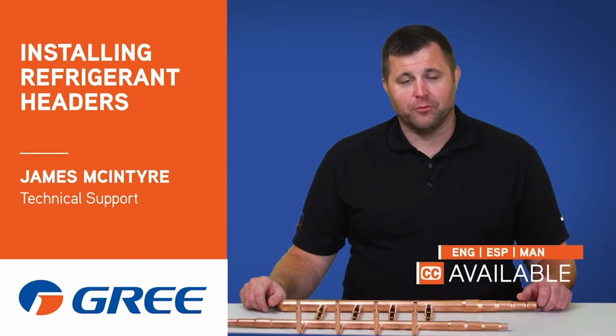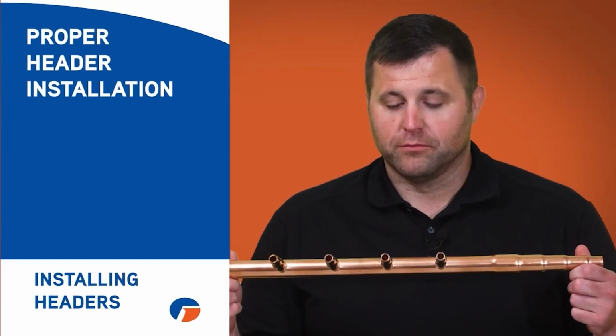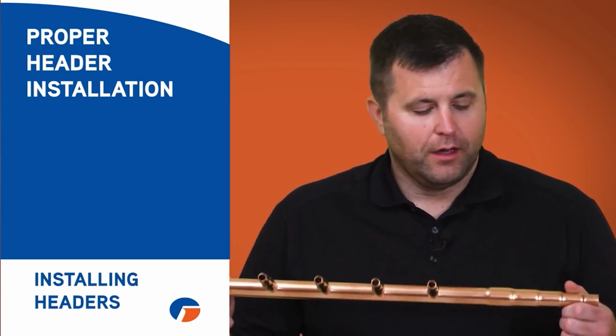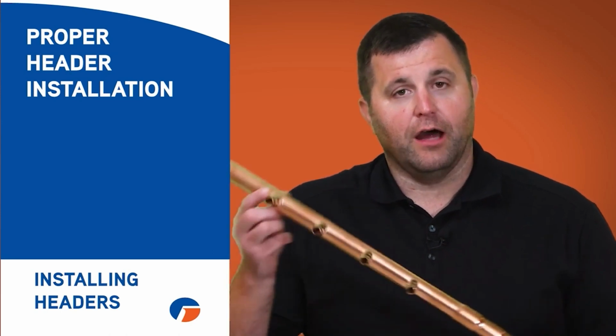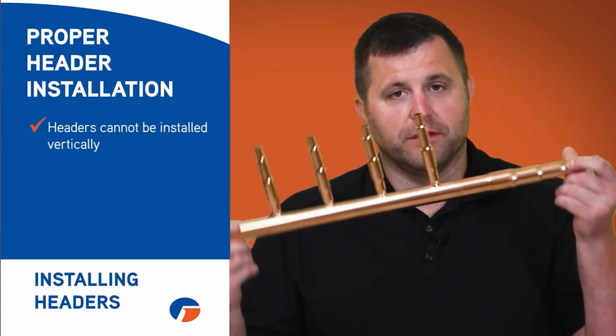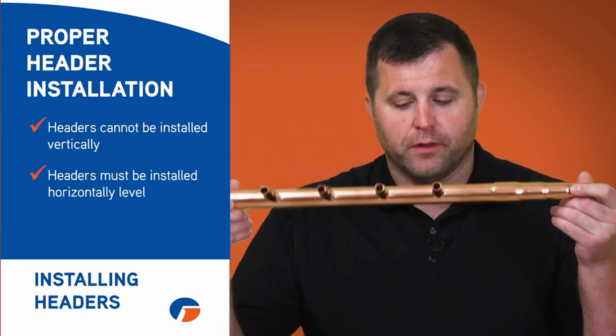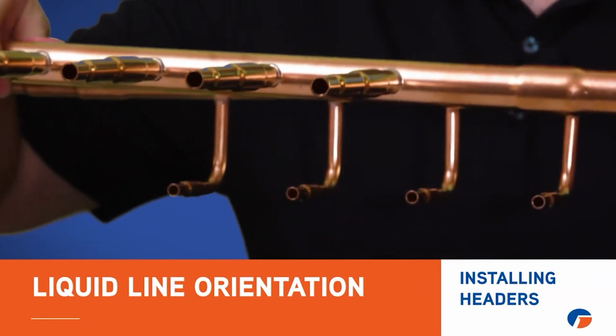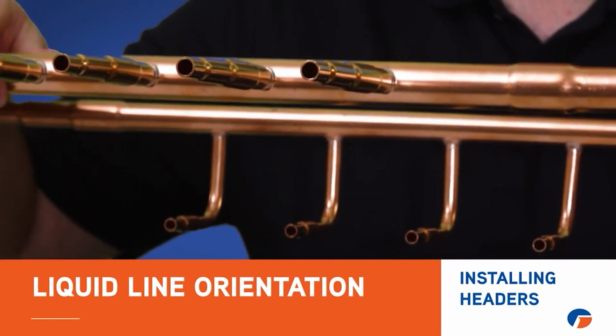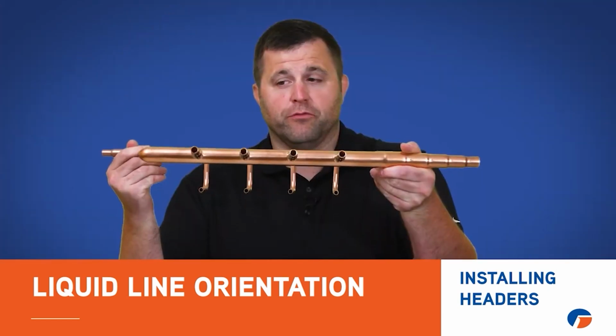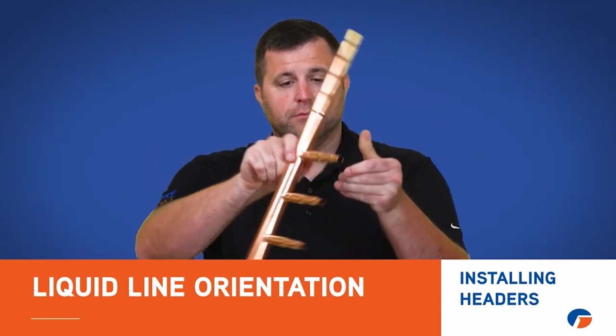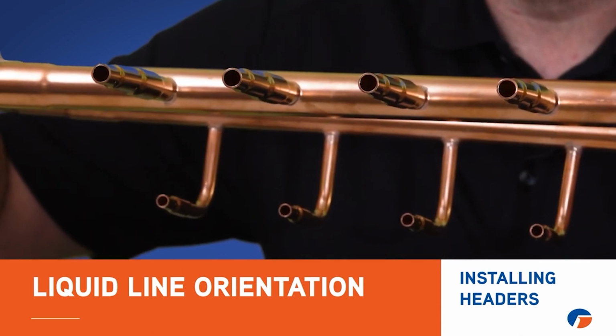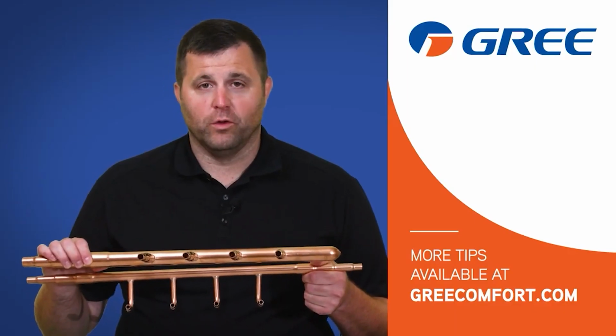All right, let's roll. Hi, I'm James from GREE with an installation tip to make your MultiPRO job easier. We've got refrigerant headers. These headers are used to connect multiple indoor units, but they have to be installed in a particular way. They cannot be installed this way or this way. They must be level with the ends pointing out just like this. The liquid line header must be installed in this orientation so that the liquid line will go below the suction lines and into the indoor units. If you need that to be reversed, you simply flip your suction header so that the piping comes in from the other side, and then you again place your liquid header so that it sits where the liquid line comes out from underneath the suction lines. If these are not installed correctly, the system will not work properly.